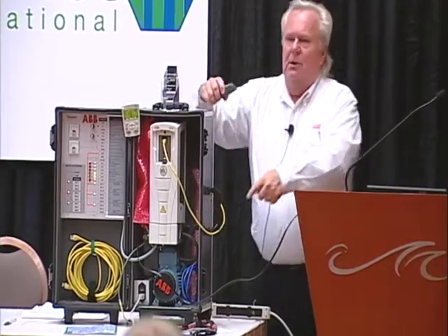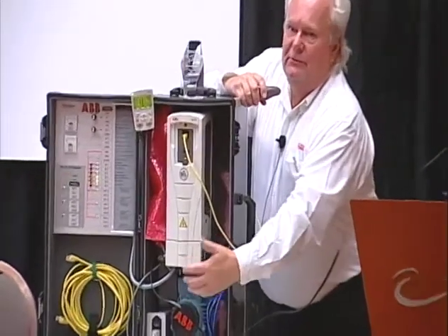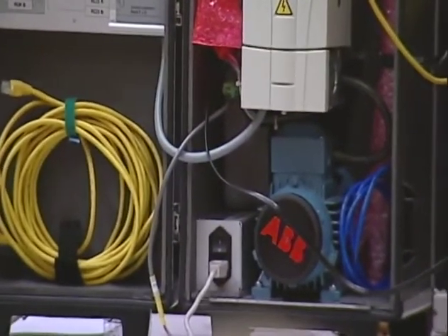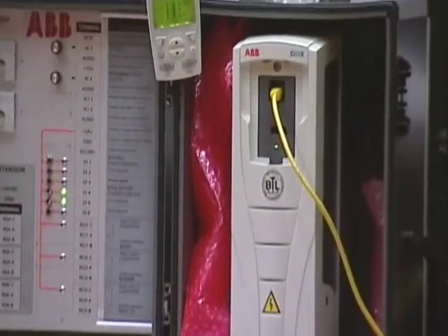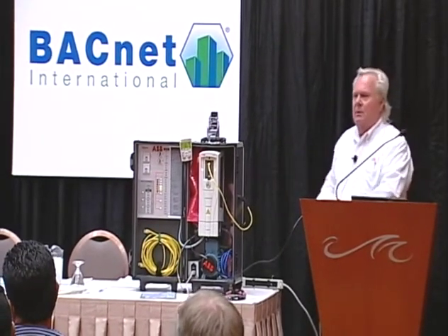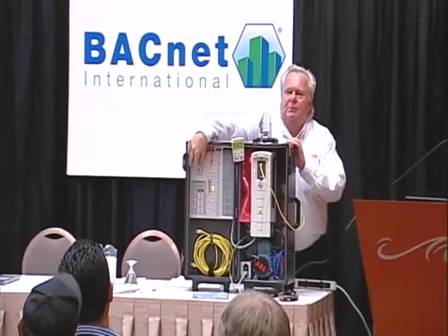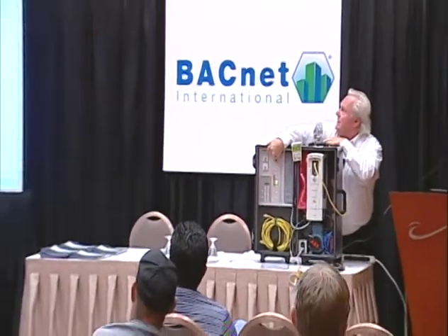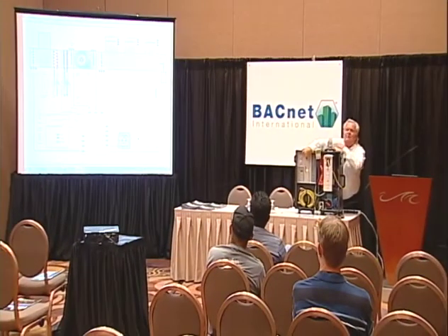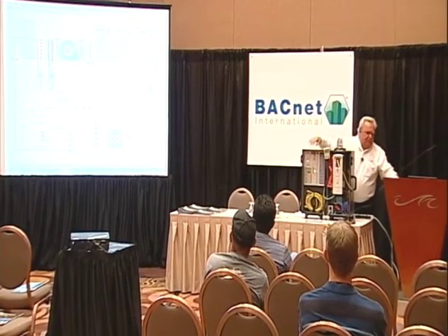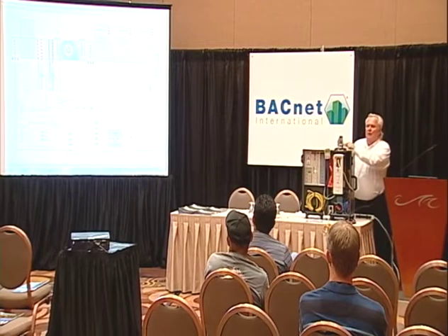Okay, and there's a little 115 to 240 volt step-up transformer in here because this is a 240 volt drive, okay? So, wired directly to the VFD, I have my static pressure sensor. It's wired into analog input 1. And what that's simulating then is the VAV boxes closing down and adjusting the duct static pressure. So as I grab this top pot on my demo case and tweak it, you'll see the VAV dampers. So pressure's going up because the dampers are closing, right? As the dampers open up, my static pressure feedback that's wired directly to the VFD goes down.